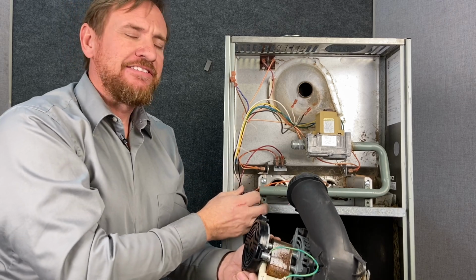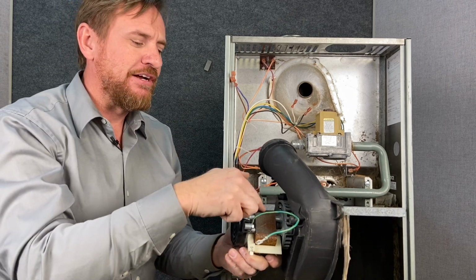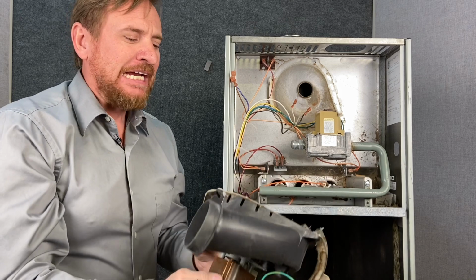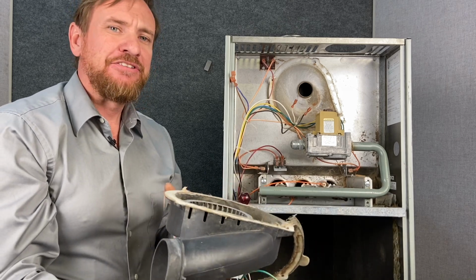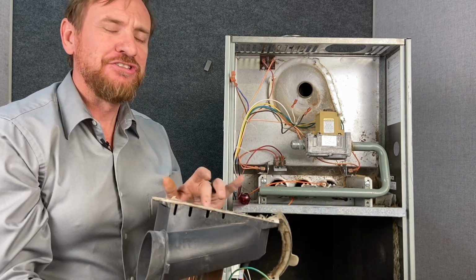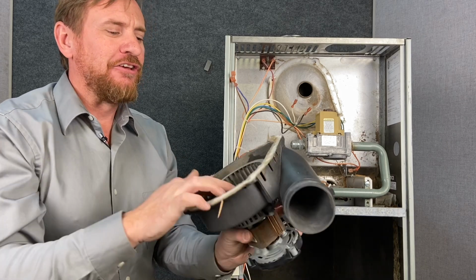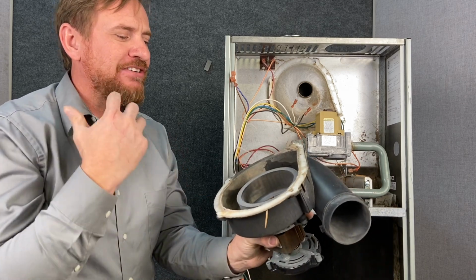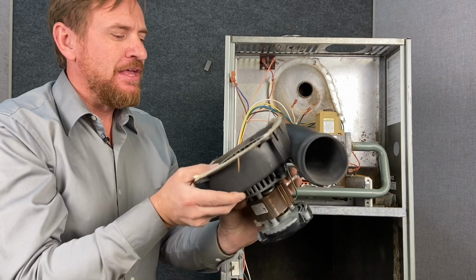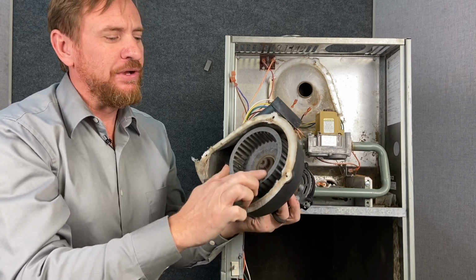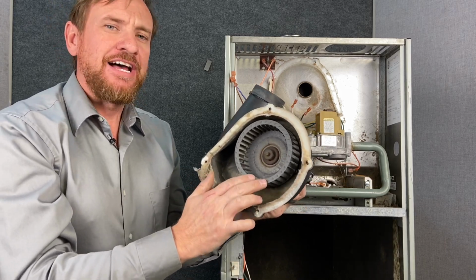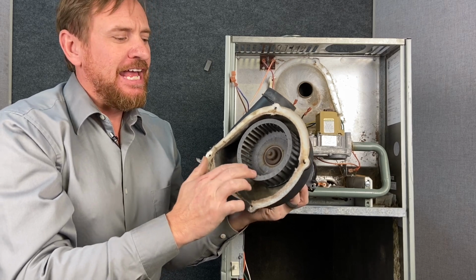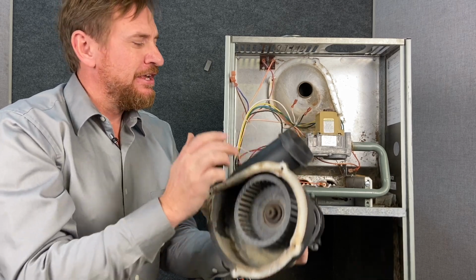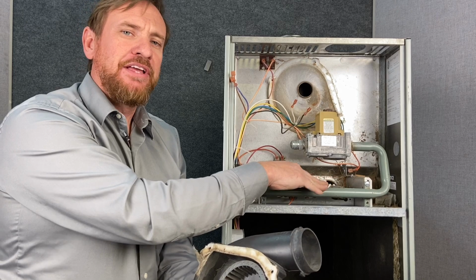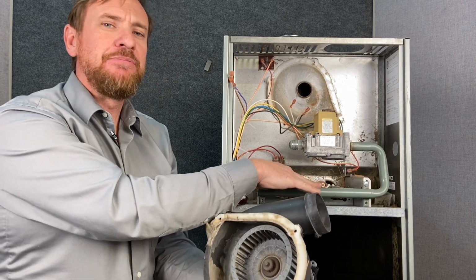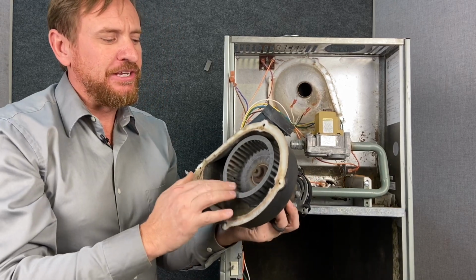So the mechanic stethoscope I like, you put it in the ears, metal rod touches it, you can hear the bearings. Can't really describe how a bad bearing sounds, but over time you hear enough good ones and you'll know when something doesn't sound right. This one I can spin it and I can just hear that it doesn't sound right. On this, notice that this wheel is very clean. Most of the time they're going to be in really good condition. If you have soot built up in here, you're having a problem with the combustion or the gas pressure in that system. Something needs to be adjusted. But usually these are pretty clean.